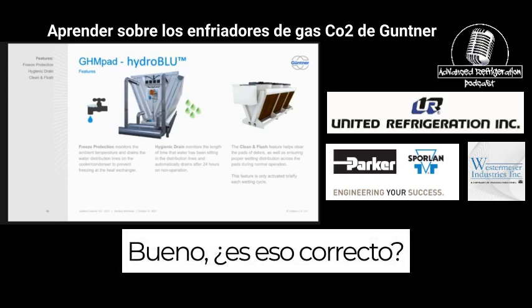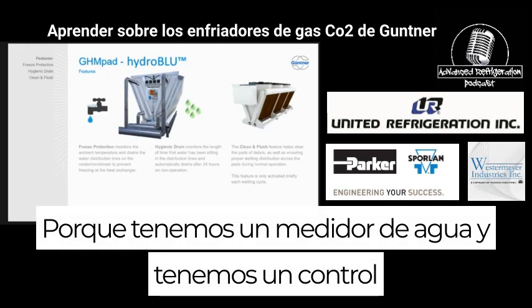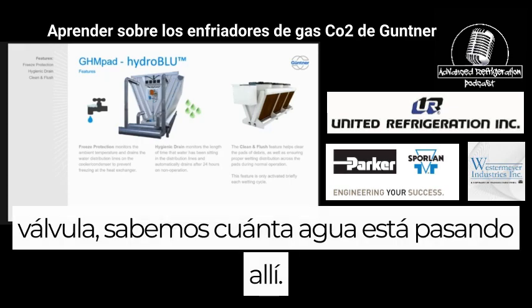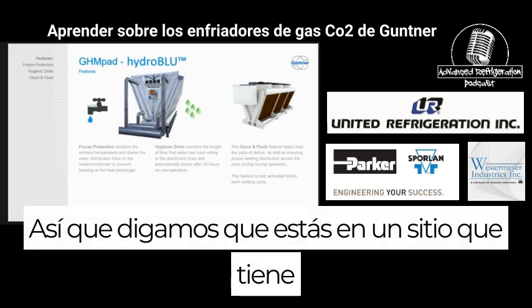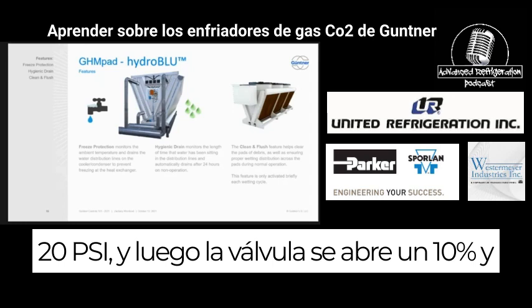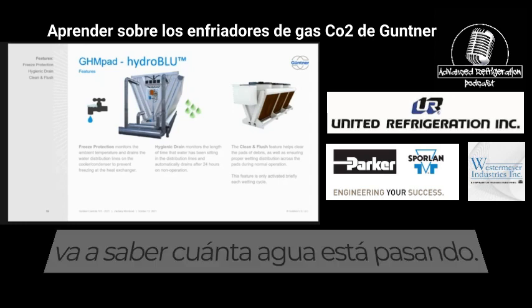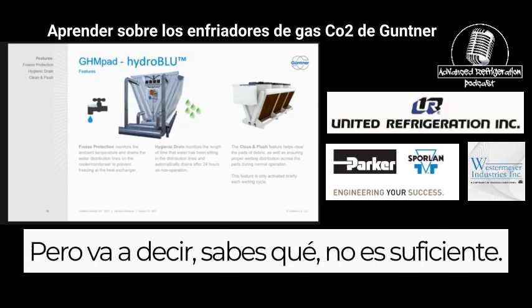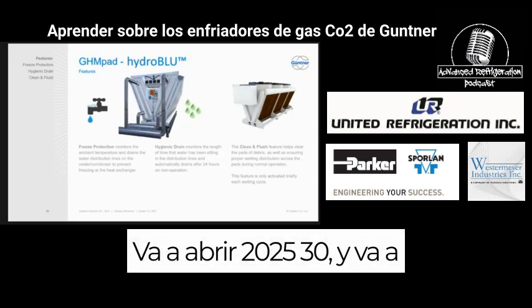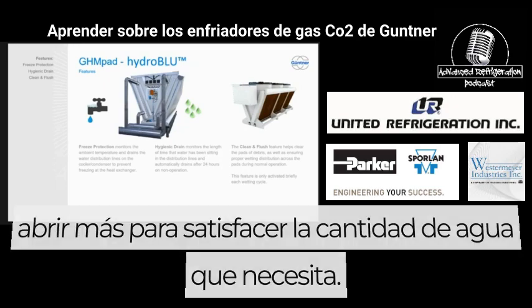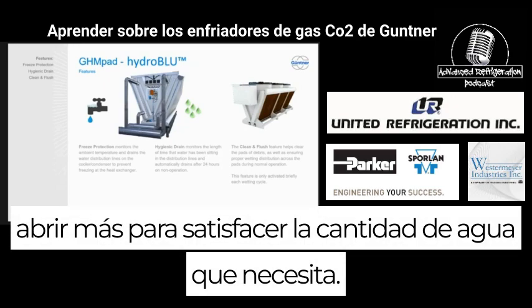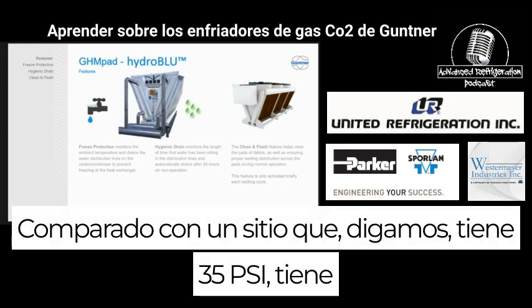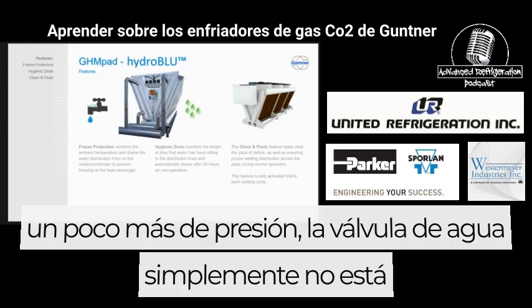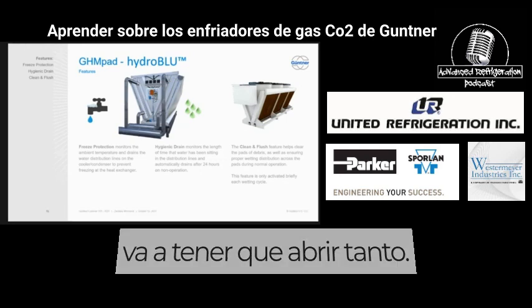Well, is that correct? Because we have a water meter and a control valve, we know how much water is going past in there. So let's say you're at a site that has 20 PSI. The valve opens up 10% and the meter knows how much water is going through, but it's going to say, you know what? It's not enough. It's going to open up 20, 25, 30, and open up more to satisfy how much water it needs, compared to a site that, say, has 35 PSI, with a little bit more pressure. The water valve just isn't going to have to open up as much.